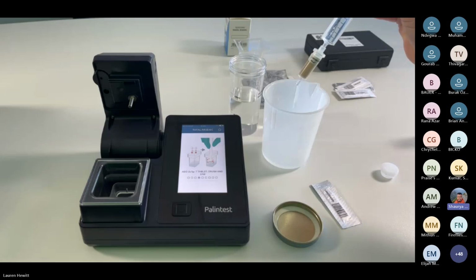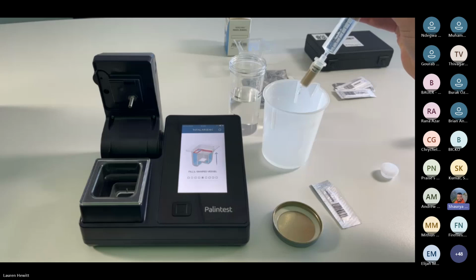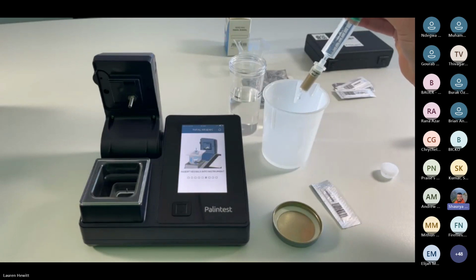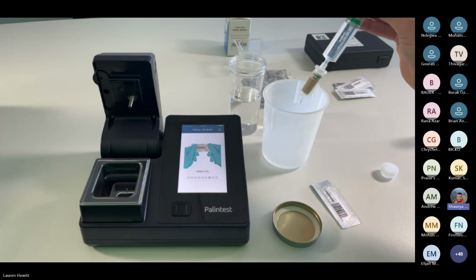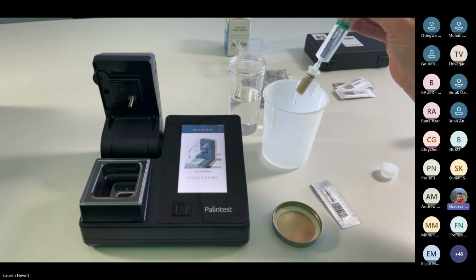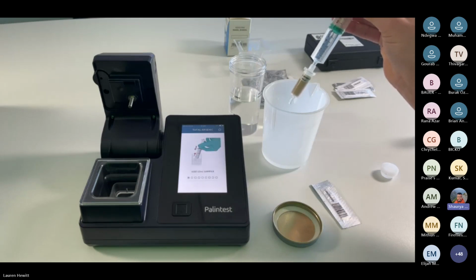Now you will see at the speed that this is being performed, this is really important because there is some metal interference that can interfere with this test, and this exchange cartridge has an exchange resin in there that removes those metal interferences, but it does allow arsenic to pass through because of the different type of charge in there. Just going to flush through that 4, and then we'll get to the 6.